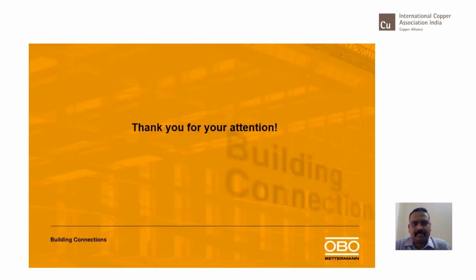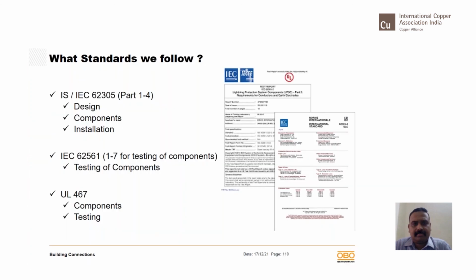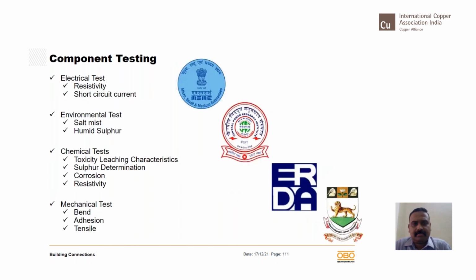This is very important. The standard we have to follow is 62305, in IS and IEC, which is also delivered in the National Building Code. 62561 is a testing standard that can be followed for the test requirements of the equipment. UL 467 gives some good practices which can be adopted for earthing systems. There are several tests where government laboratories are available to test the system and give you a result.